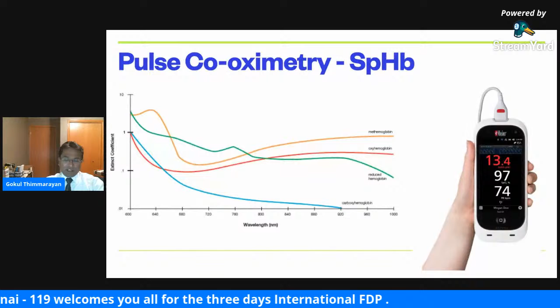Instead of using two wavelengths of light, multiple other wavelengths are utilized, up to 7 wavelengths of light. And when it passes through the tissue, with the variation in absorption, and the amount of light that reaches the sensor with the different wavelengths, it is extrapolated, and it is possible to calculate the amount of hemoglobin present in the blood. Hemoglobin, carboxyhemoglobin, methemoglobin, all of this could also be calculated. And this is pulse co-oximetry. It's essentially the same. Instead of using two wavelengths, multiple other wavelengths of light are used to get the information. So pulse oximetry and co-oximetry give the amount of oxygen and the hemoglobin and the various other forms of hemoglobin in the blood.